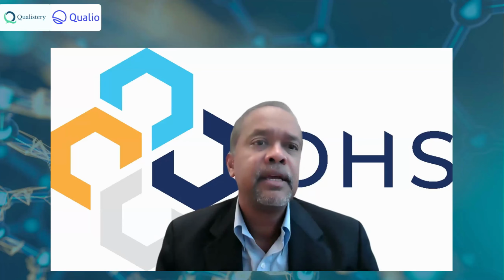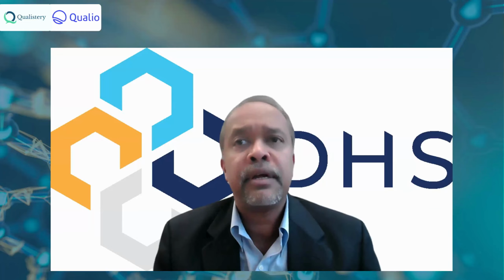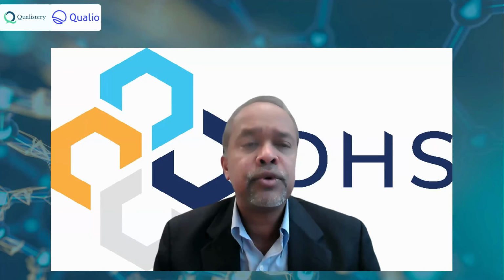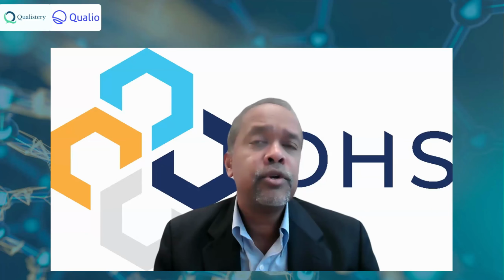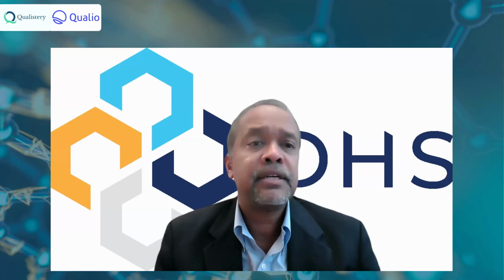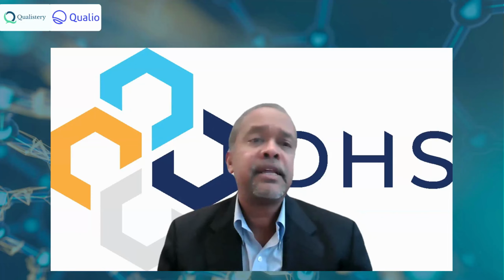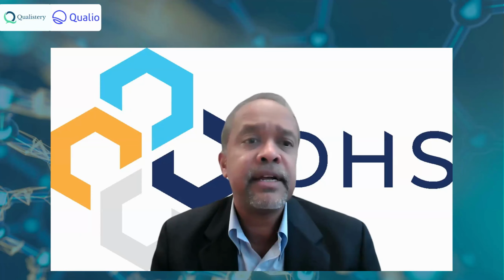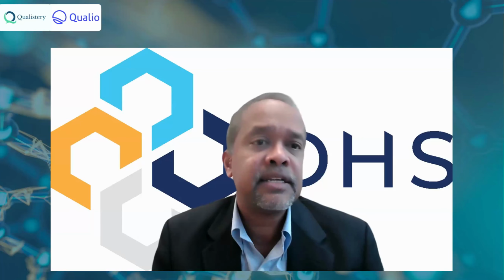It does apply. And of course, risk management applies as long as a regulatory body is going to regulate the product. So SAMD could be a low risk SAMD class 1. Still risk management applies. Class 2, it does. Or maybe it's a de novo. You will determine the risk later because there is no predicate. So it still applies. So yes, answer is yes.